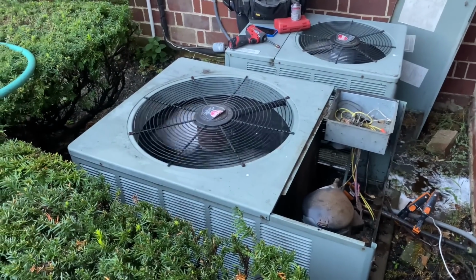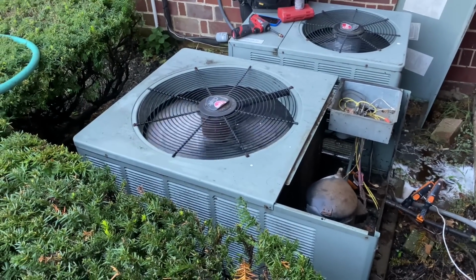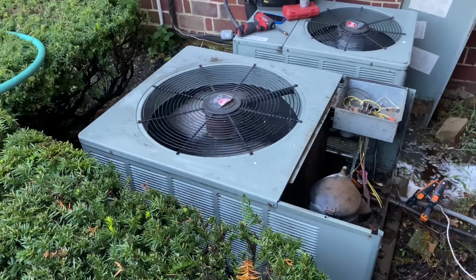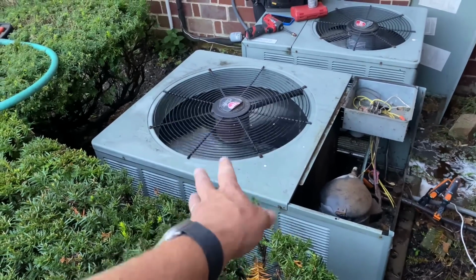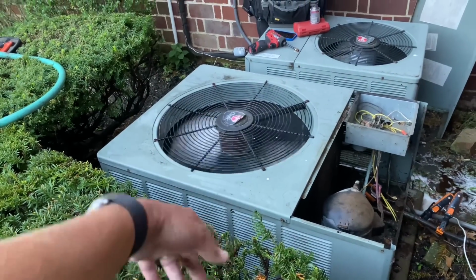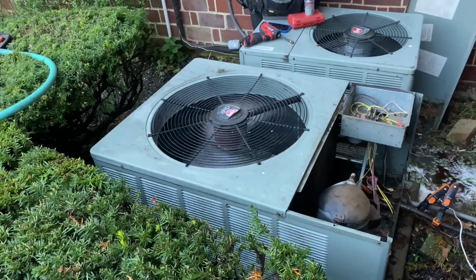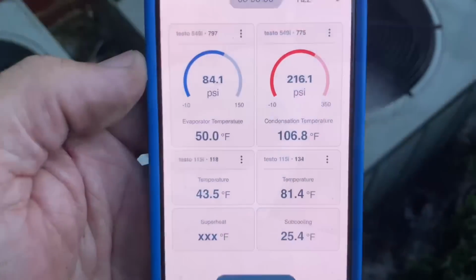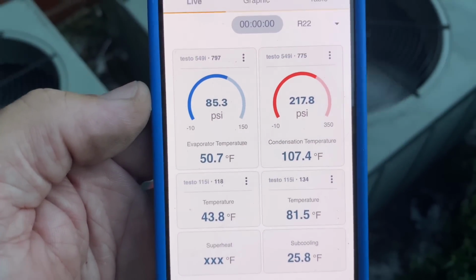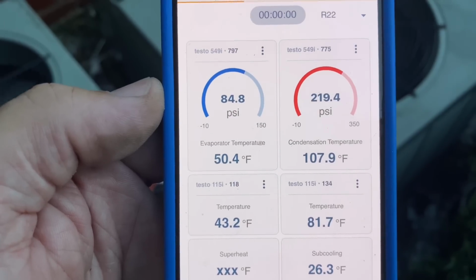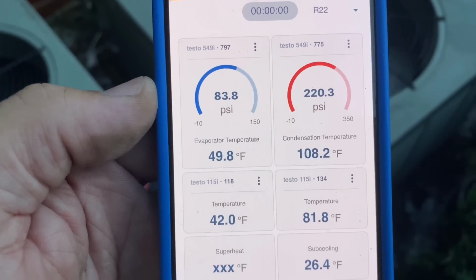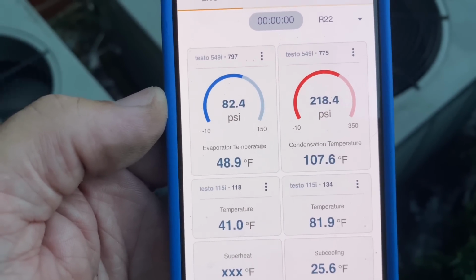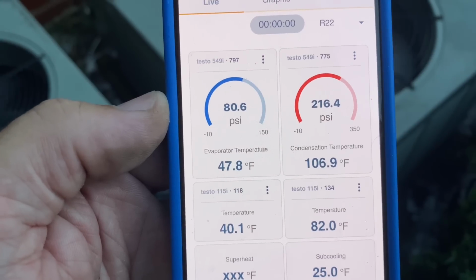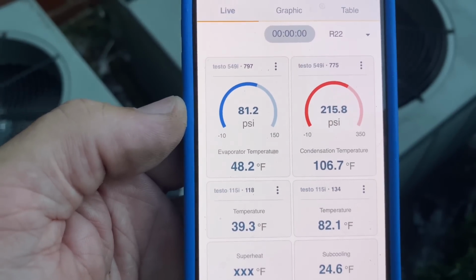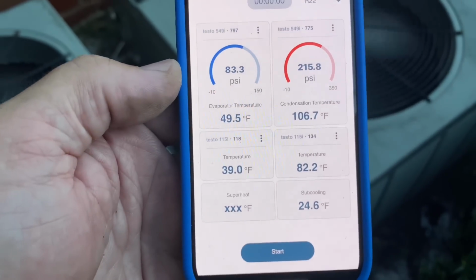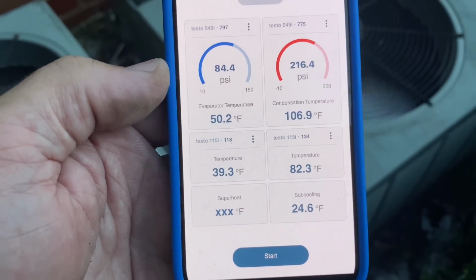Hopefully I gave her a breath of life and we'll be all right with the pressures. It's going to naturally be low right now because the coil is nice and cold, but hopefully that helps. System is running for a couple minutes, 220 PSI in, staying around 220, dropping now to 216, 81 PSI on our low side, 25 degrees subcooling.